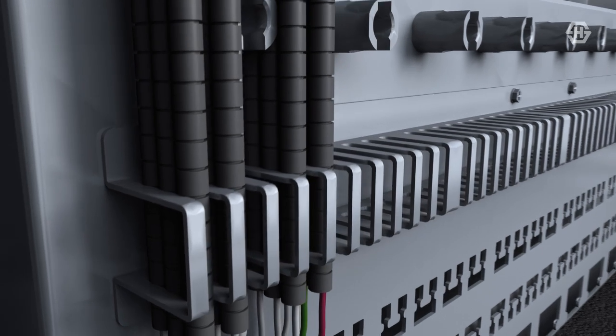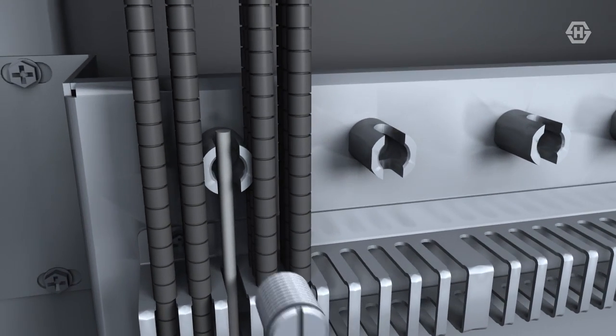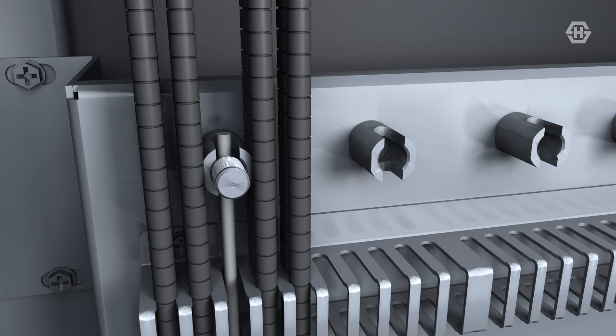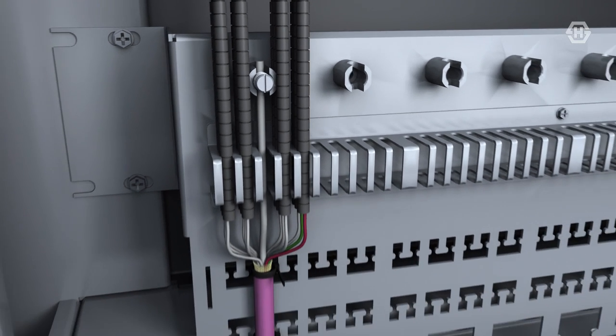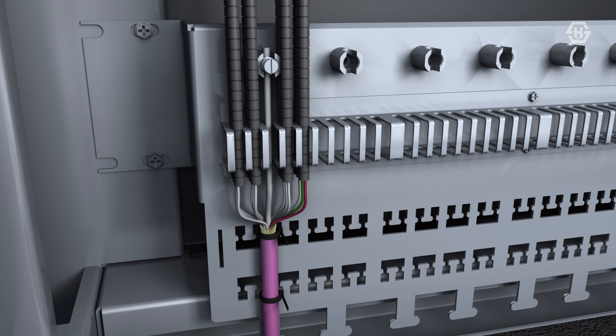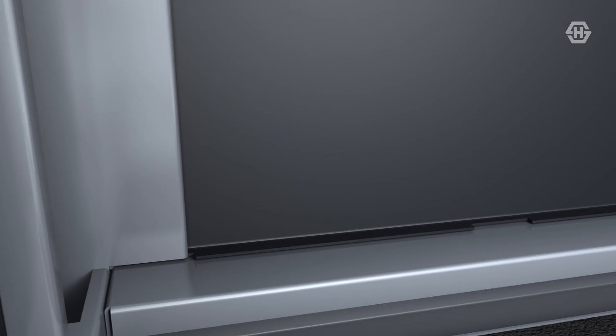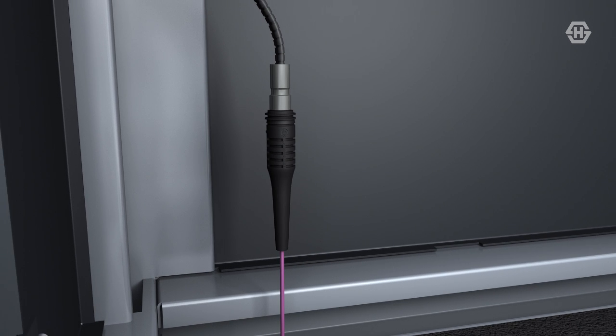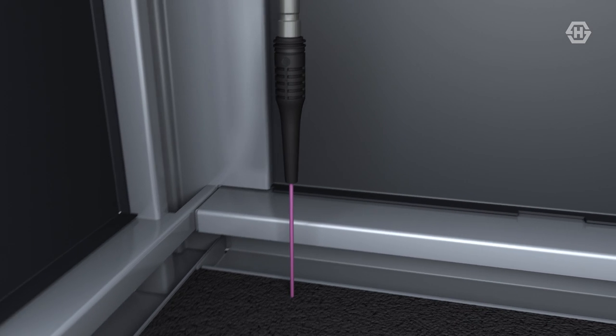Finally, the central strength member of the cable, be it a fiberglass rod or Kevlar, can be clamped into place so that force placed on the cable outside of the cabinet has no impact on the internal fibers. This three-tier fixing method is the most comprehensive and repeatable method of protecting high fiber count cables within a high-density fiber management rack. Cables which are pre-connectorized, such as MPO cable systems, require considerably less protection than loose tube cables.